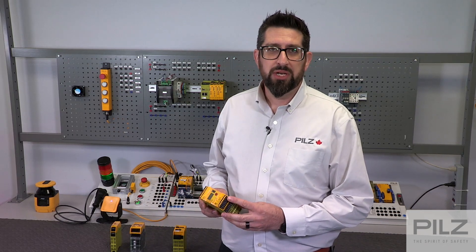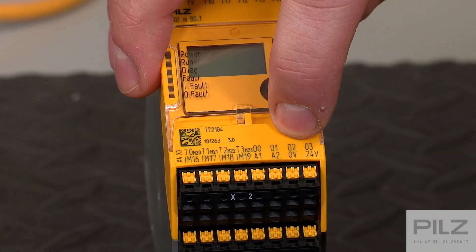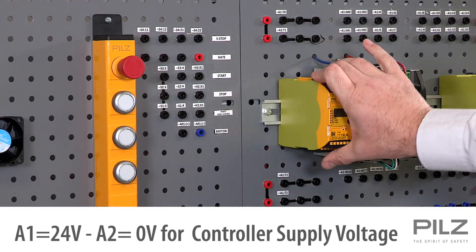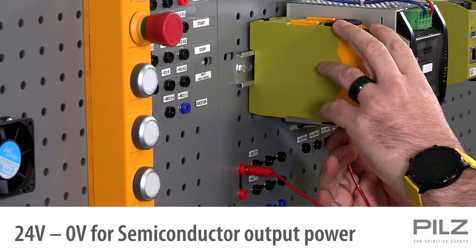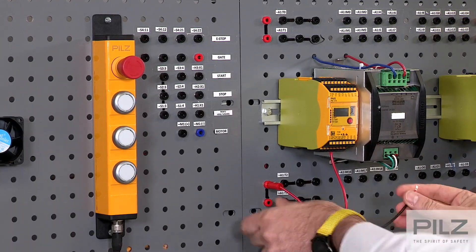The first step in wiring your PNOZ Multi2 controller is the power supply. The units all have two separate power supply connections. First, terminals A1, which is 24V, and A2, 0V, power the controller itself and the communication bus. The 24V and 0V terminals power the outputs of the controller. These can be powered using a single power supply or isolated by using two, depending on your application requirements.